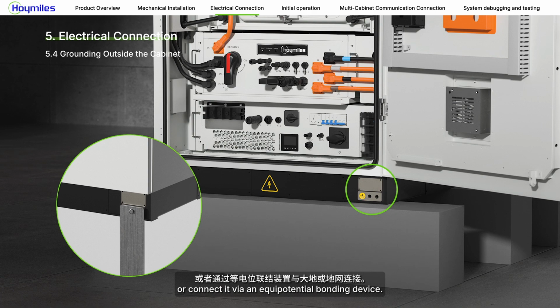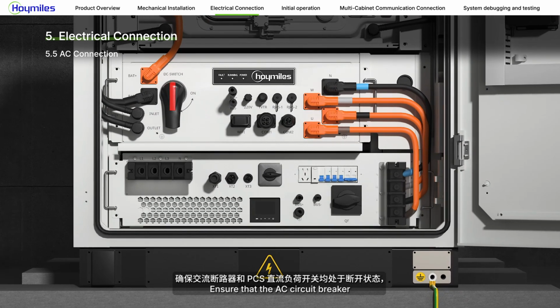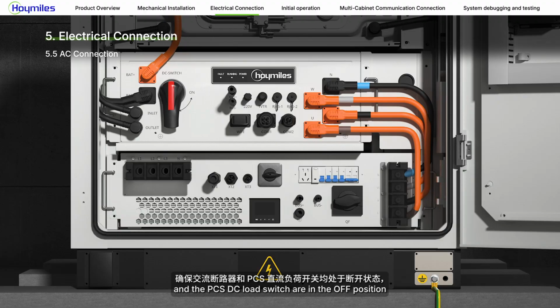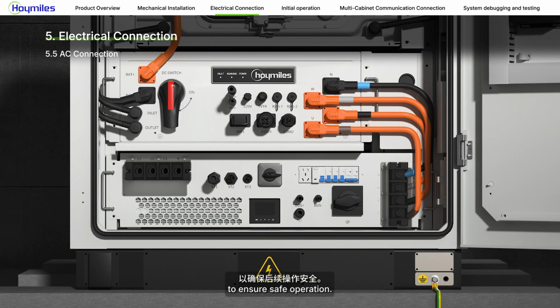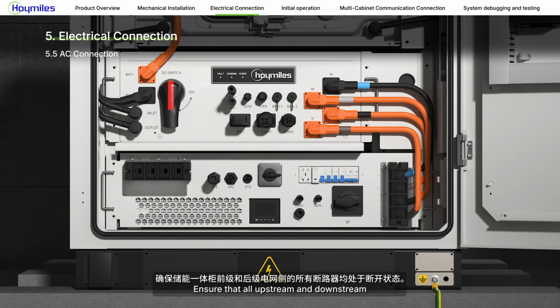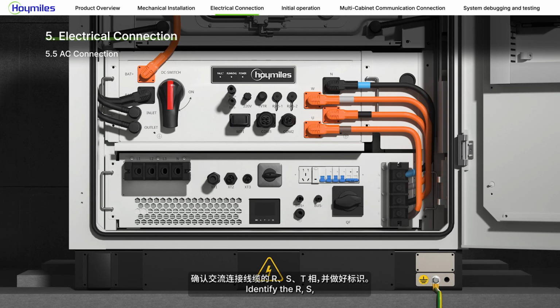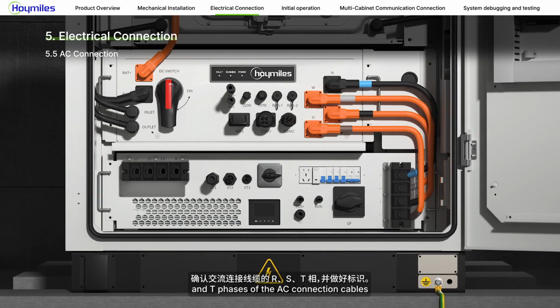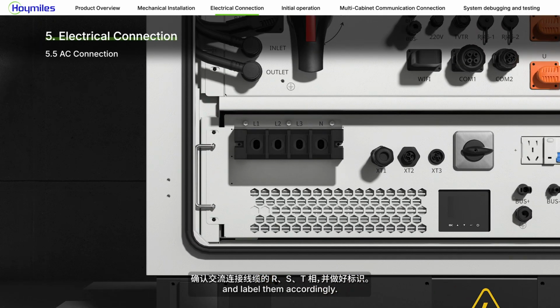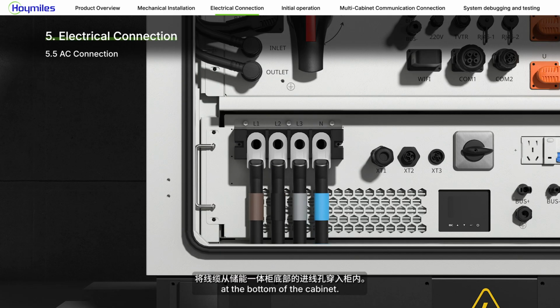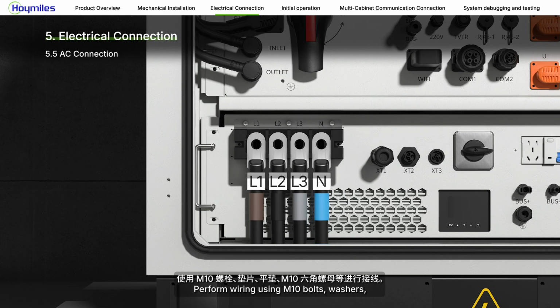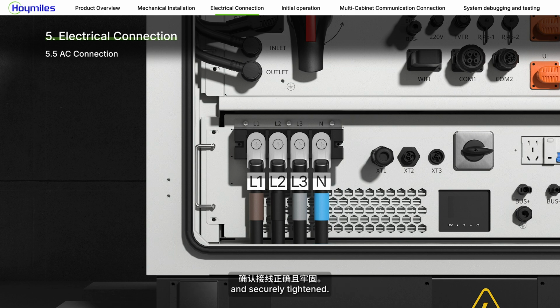an equipotential bonding device. Ensure that the AC circuit breaker and the PCS DC load switch are in the off position to ensure safe operation. Ensure that all upstream and downstream grid side circuit breakers of the energy storage system are disconnected. Identify the R, S, and T phases of the AC connection cables and label them accordingly. Route the cables through the cable entry at the bottom of the cabinet. Perform wiring using M10 bolts, washers, flat washers, and M10 hex nuts. Confirm that all connections are correct and securely tightened.